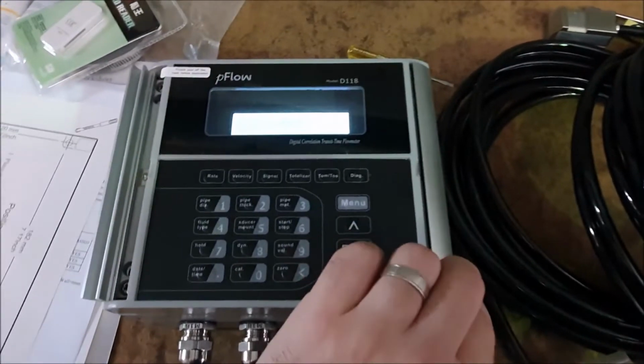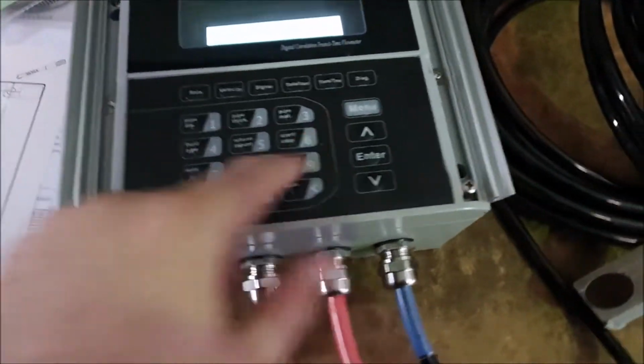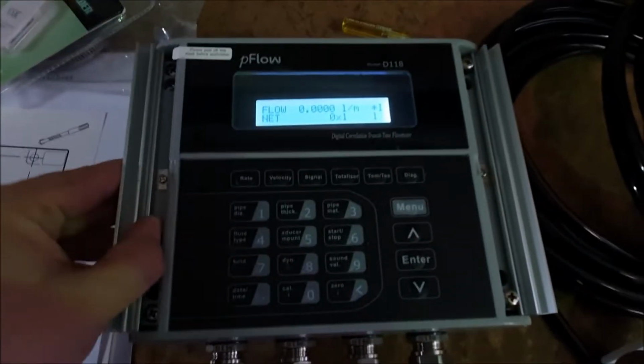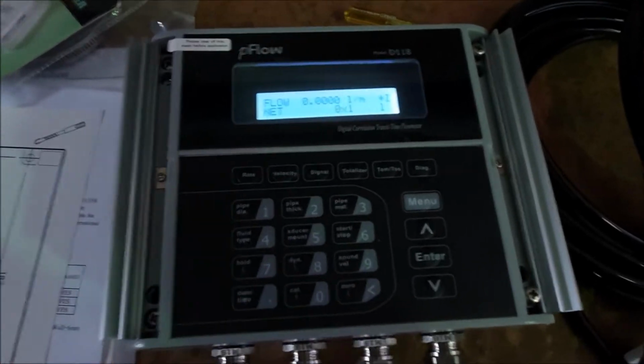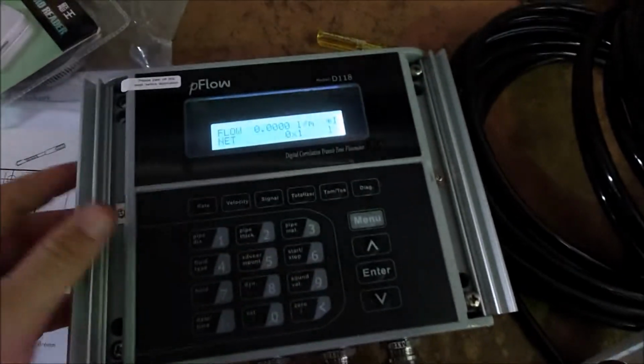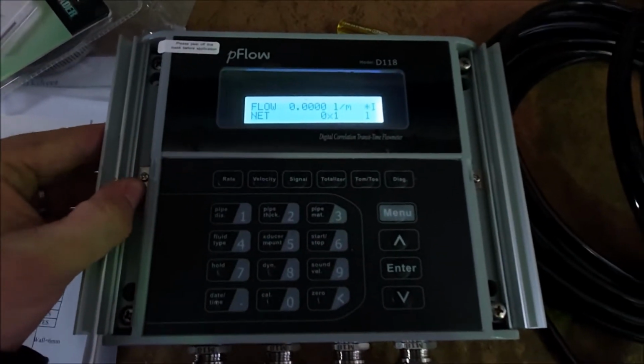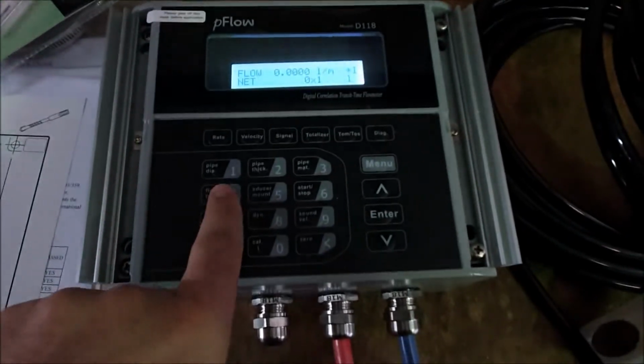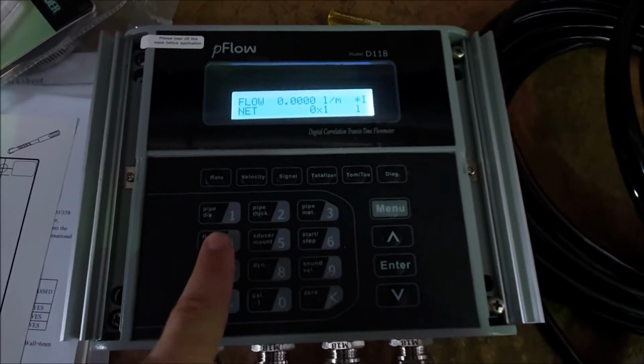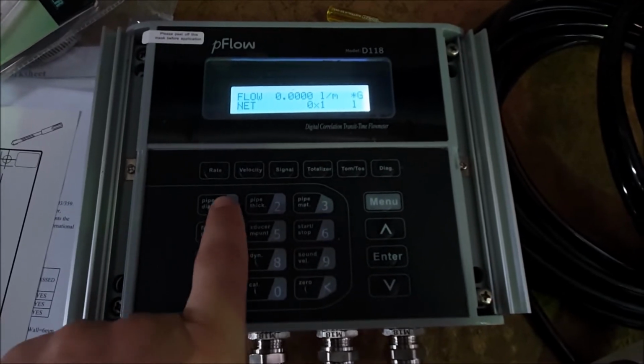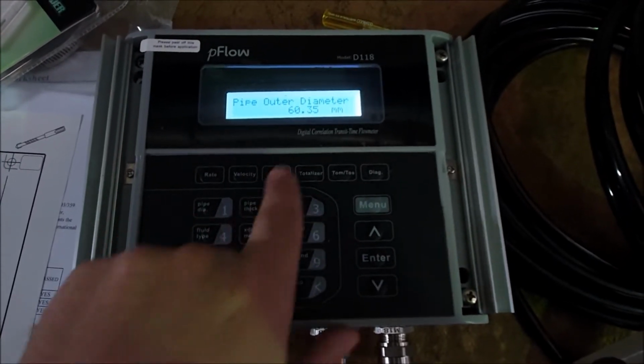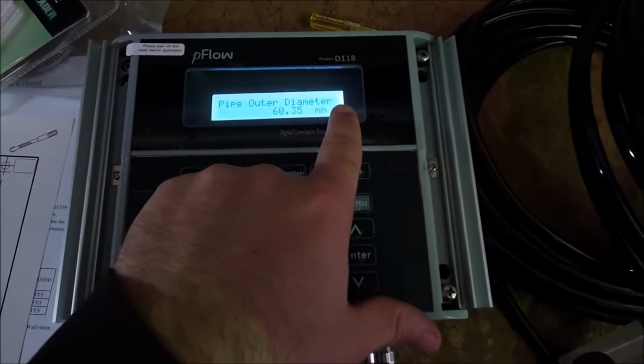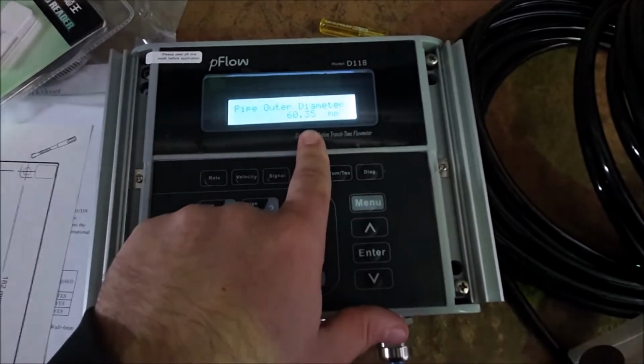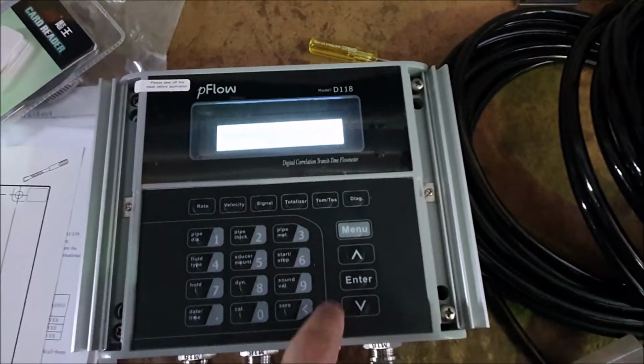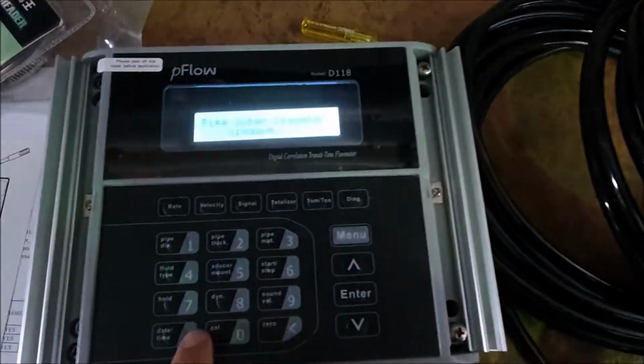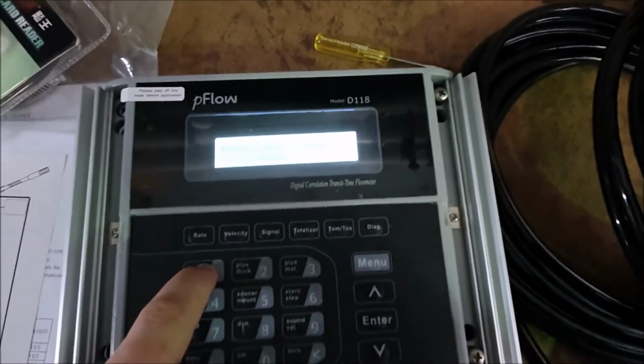So if we flip the lid down, we have the keypad here on the front. Okay, so there's a couple parameters, I suppose, that the flow meter needs to know in order to calculate your flow correctly for what you've got it installed on. So the first menu you're going to want to go into is your pipe diameter. Okay, so you can get this by pressing 1, and you'll see it now says pipe outer diameter. We need to set what the diameter of the pipe is. Okay, you can also get to this by pressing menu and then manually typing that menu number, which is 11.